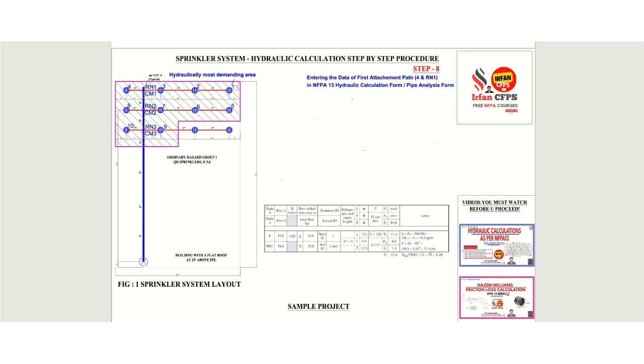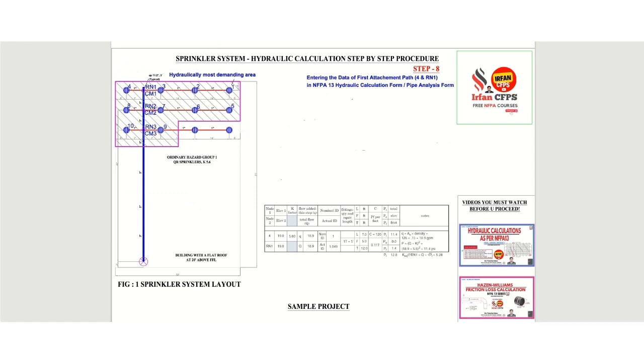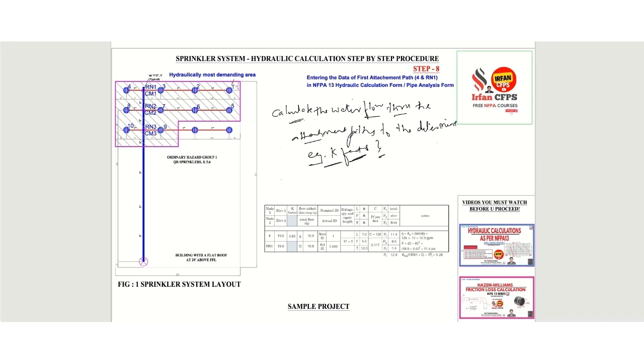Now we are going to discuss Step 8. This will be interesting since we are going to enter the data of the first attachment path, which is node 4 to RN1, in the NFPA 13 hydraulic calculation form — also called the pipe analysis form. What we are going to do initially is calculate the water flow through the attachment paths to determine the equivalent K factor.